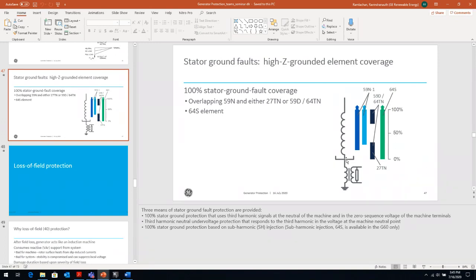Yes, I do. And it's very important that I detect that fault, because what has just happened? By having a ground on the neutral, I've bypassed my high impedance ground, because now I've connected the neutral to the ground. So my generator is not a high impedance grounded system anymore. It's a solidly grounded system. So if I have another ground fault within my generator, that can cause lots of fault current to flow into my generator, maybe even more than my three-phase fault current, and cause a lot of damage. So I need to detect faults all the way to the neutral of the generator winding to detect any type of ground fault, because that's just an accident waiting to happen if I neglect to detect a ground fault on the neutral.